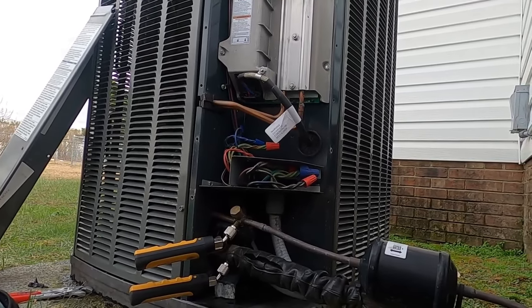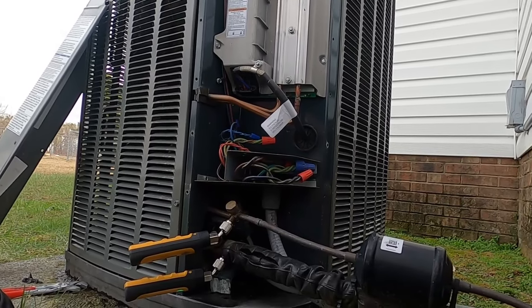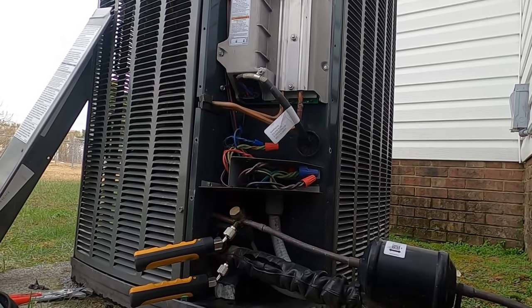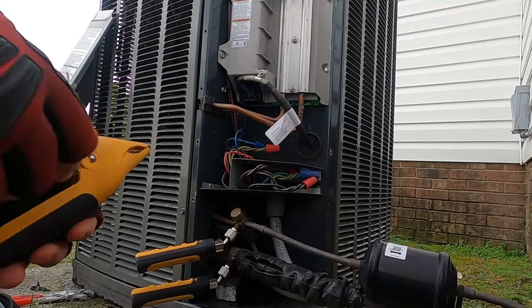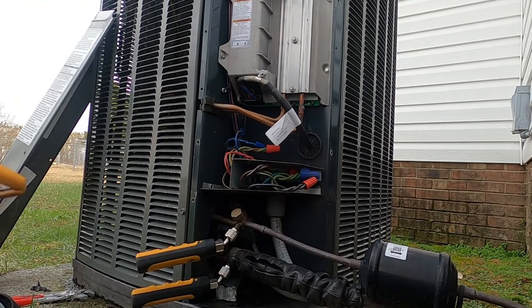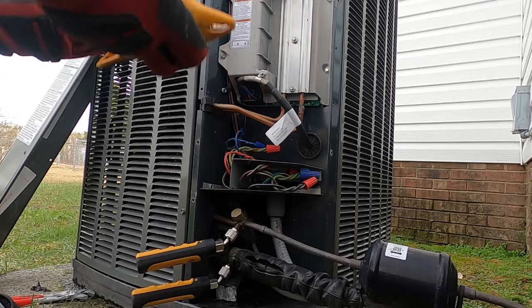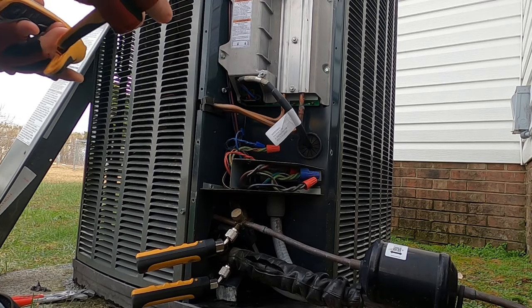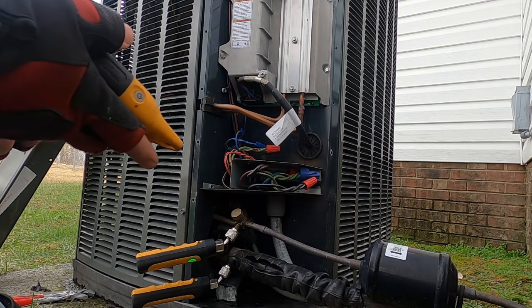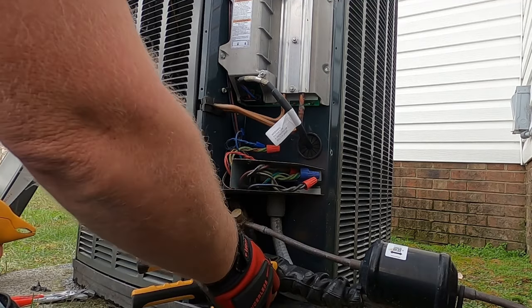Last thing we did on this unit was the solenoid for the reversing valve. It's not a typical 24 volt valve. I'll show you that here in a minute. It is a communicating kind of a one-step valve. What it does is it gets a quick pulse.